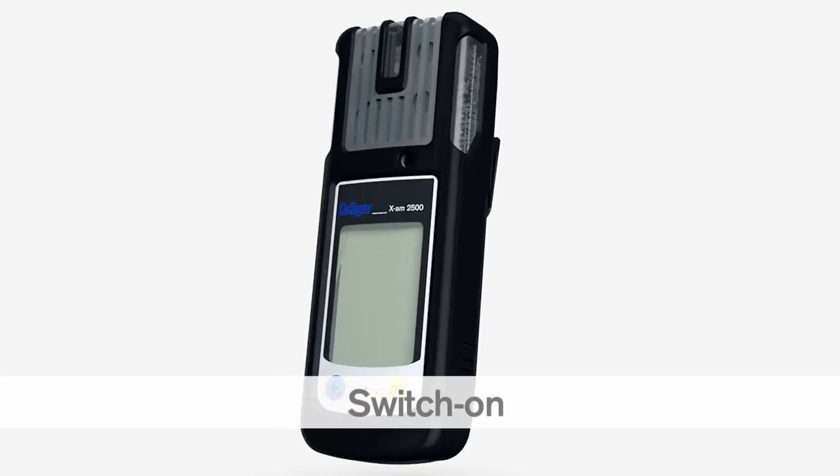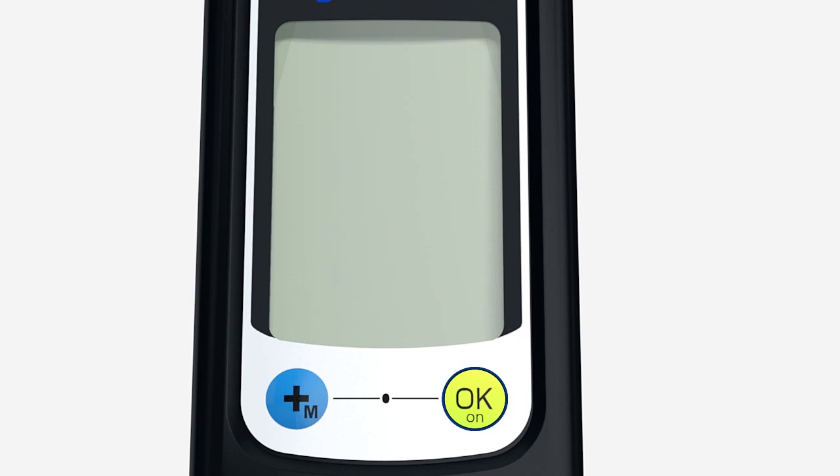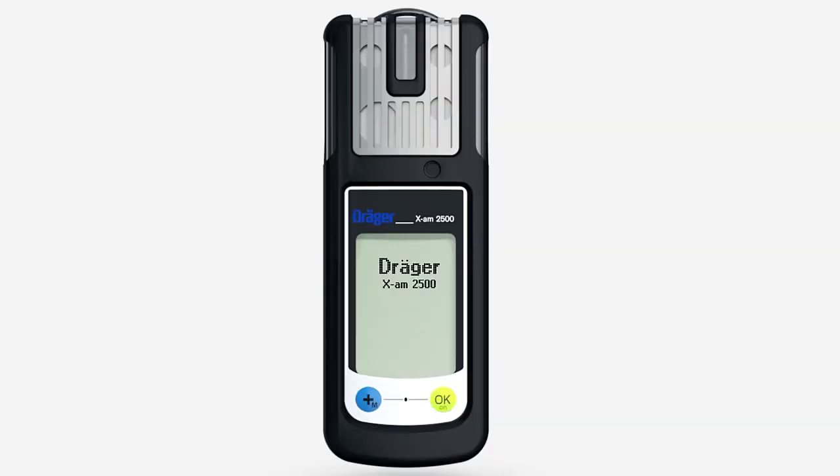To switch on the X-am 2500, press and hold the OK key for 3 seconds. A countdown is shown in the display. The LEDs flash and the vibration alarm vibrates to show that the device has been switched on. The instrument starts the boot sequence and performs an automatic self-test.